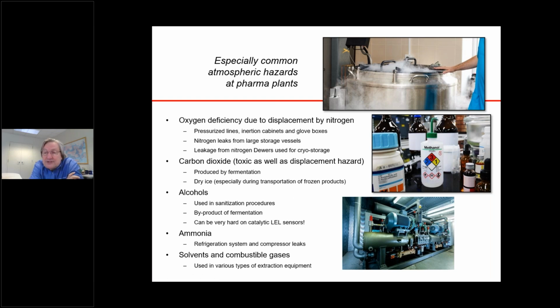Alcohols are pervasively common in pharmaceutical laboratories, in pharmaceutical production areas. It can be a byproduct of fermentation. It can also be part of sanitization procedures. We'll be talking about combustible sensors and the effects of some of these gases on LEL sensors in a little bit. But if you're using traditional catalytic LEL sensors that detect combustible gas by burning the gas on a bead, an active bead on the inside of the sensor, that bead is actually made out of alumina. It's alumina that is treated or doped with a catalytic material that allows oxidation to occur, but the bead itself is made out of alumina.